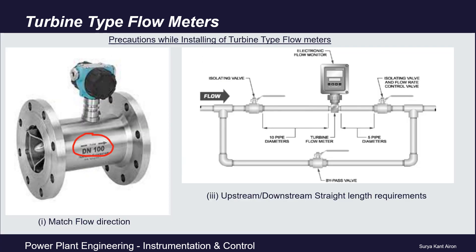Coming to the installation guidelines: first, we have to match the flow direction with the arrow mark on the turbine type flow meter. Second is the straight length requirement — the straight pipe section before the turbine flow meter should be at least 10 times the pipe diameter, and downstream should be at least 5 times the pipe diameter. For example, if the pipe diameter is 100 mm, the upstream straight length requirement would be 1000 mm and downstream would be 500 mm.